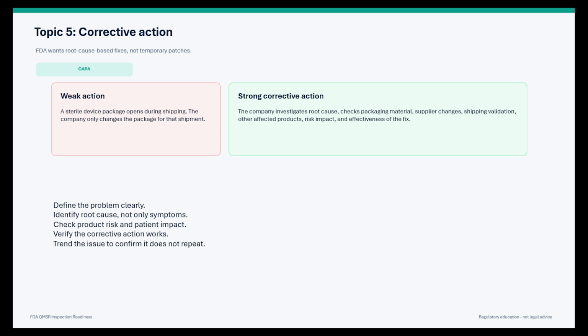The company would investigate root cause, check whether packaging material failed, review whether a supplier made changes, evaluate whether shipping validation was adequate, determine whether other products are affected, assess product risk and patient impact, and verify whether the corrective action works. After the fix, the company should trend the issue to confirm it does not repeat. For CAPA owners, the important point is connection. CAPA should connect to complaints, supplier performance, risk management, and effectiveness checks. If those links are missing, the CAPA may look like a temporary patch rather than a system-level correction.